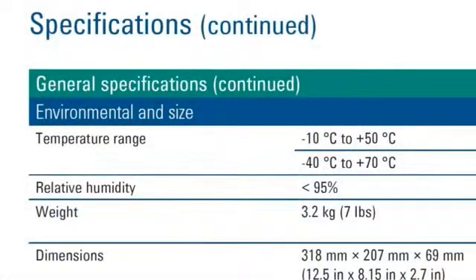Here in Australia, the ambient temperature can frequently exceed 40°C, and the temperature within a communication hut can approach 50°C. All of the measurement specifications are guaranteed for an operating temperature range from minus 10°C to plus 50°C, with battery operations specified from zero to 50°C.